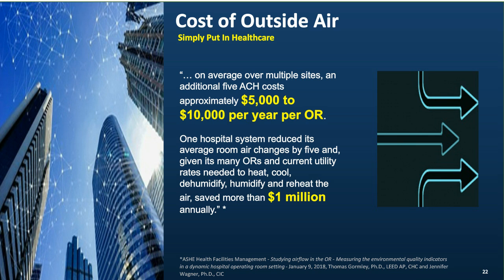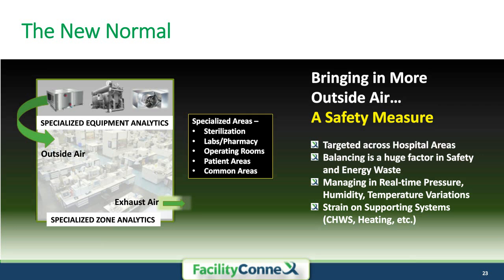This is a great way, and with the new normal that is happening, pushing the fact that outside air needs to increase and air change rates are going to help drive less infectious disease from spreading, it becomes even a higher worry moving forward, because it's being targeted across hospital areas, not just in specialized areas anymore. They want to bring more outside air into all the areas. Even enterprise and office buildings are talking about these type of aspects. ASHRAE wrote new requirements around air change rates just recently and have created new guidelines around that. So there's a huge balancing aspect that the facility engineer has to really drive when it comes to safety and energy waste.